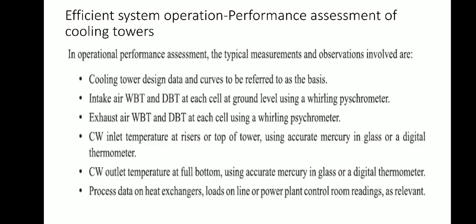Then performance assessment of cooling towers. In operational performance assessment, the typical measurements and observations involved are: cooling tower design data and curves to be referred to as basis. Intake air WBT and DBT at each cell at ground level using a whirling psychrometer.